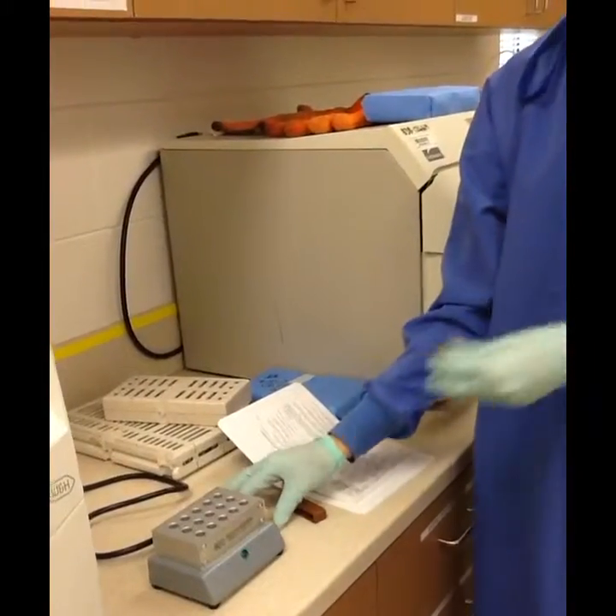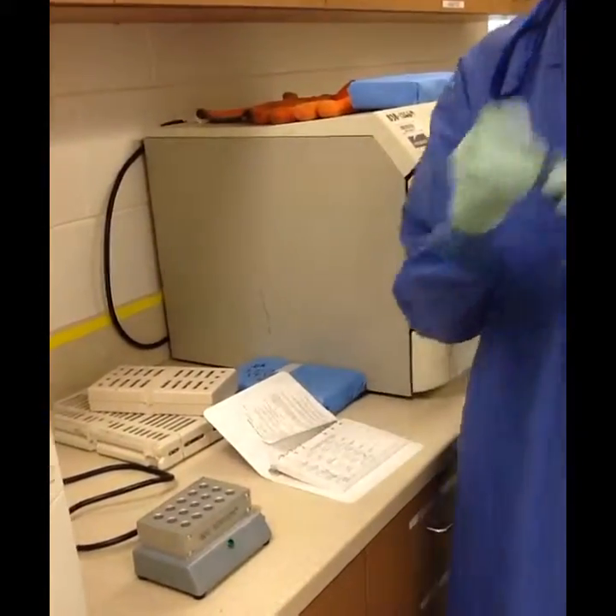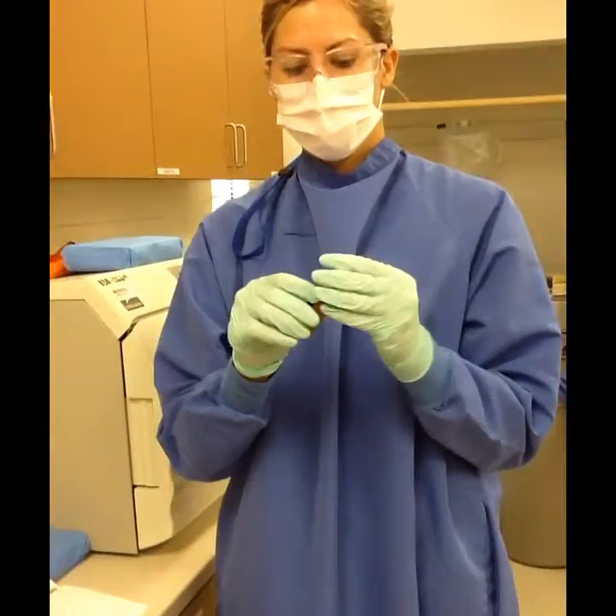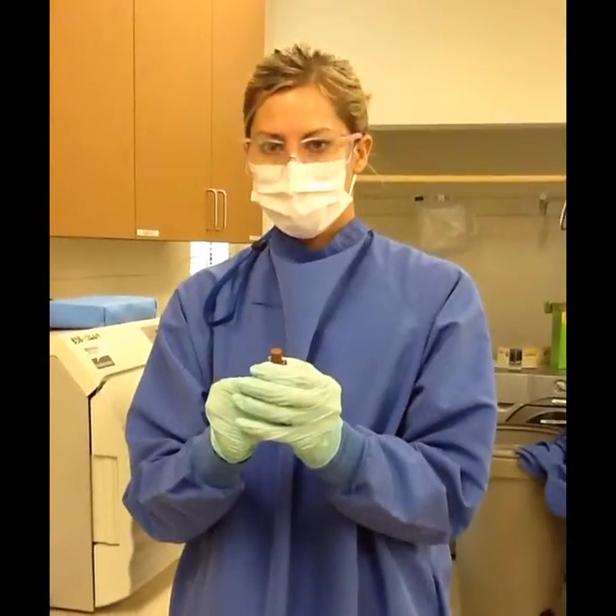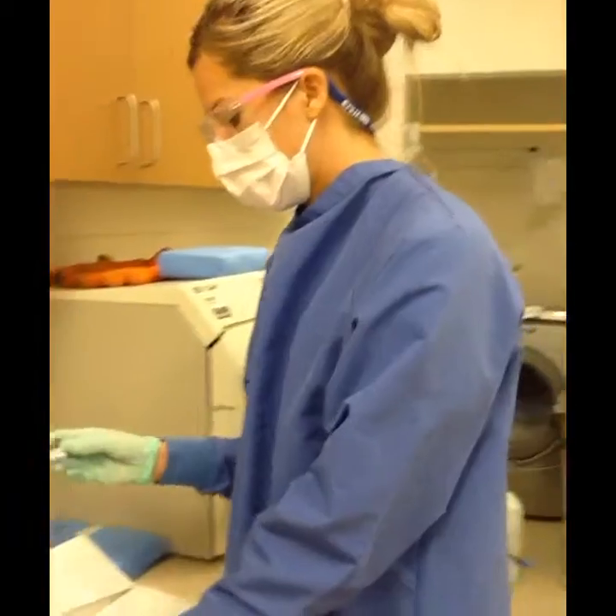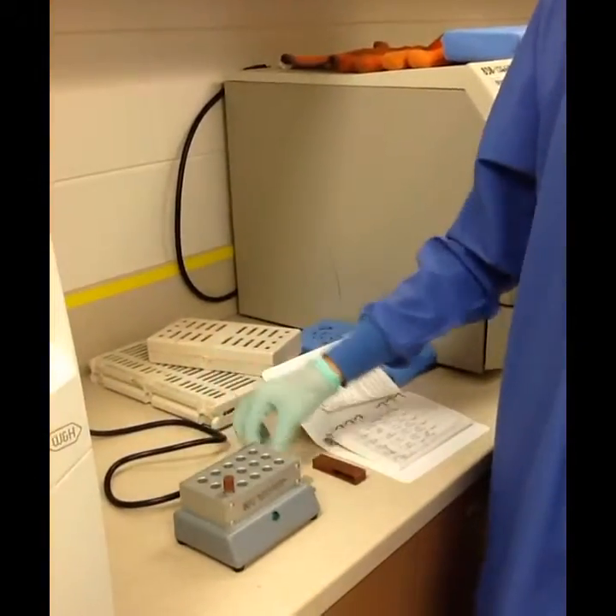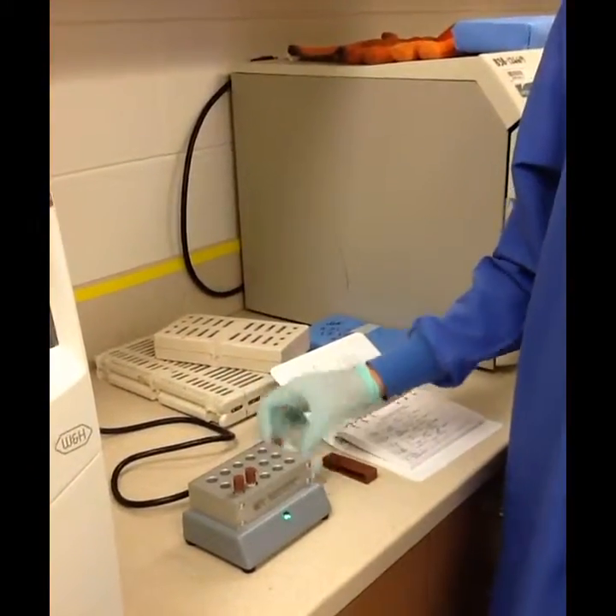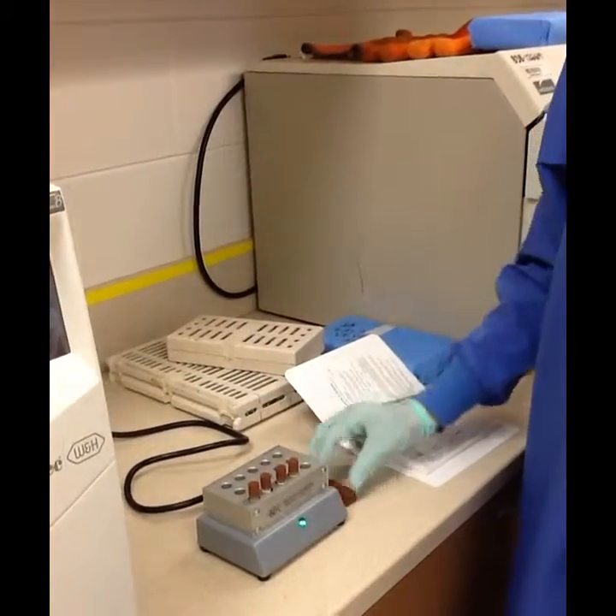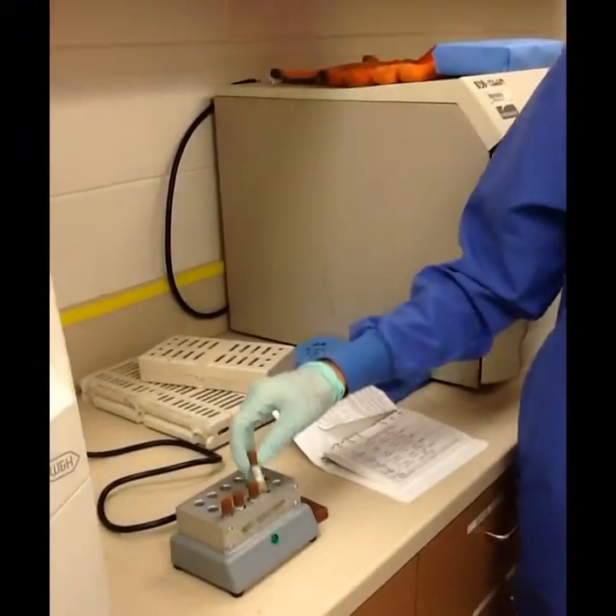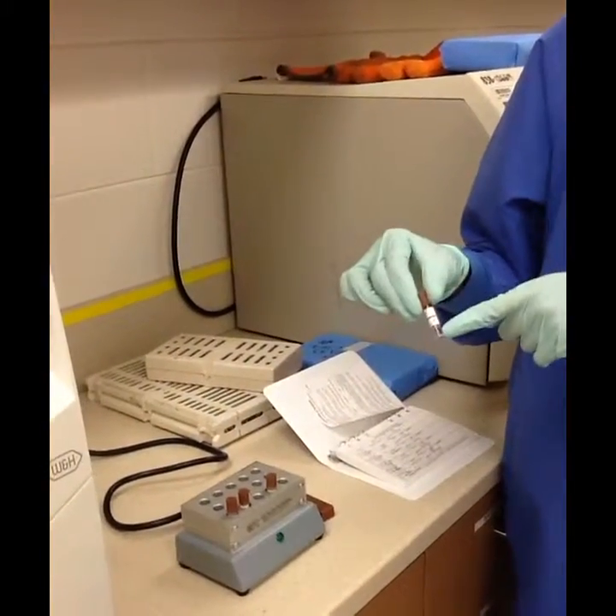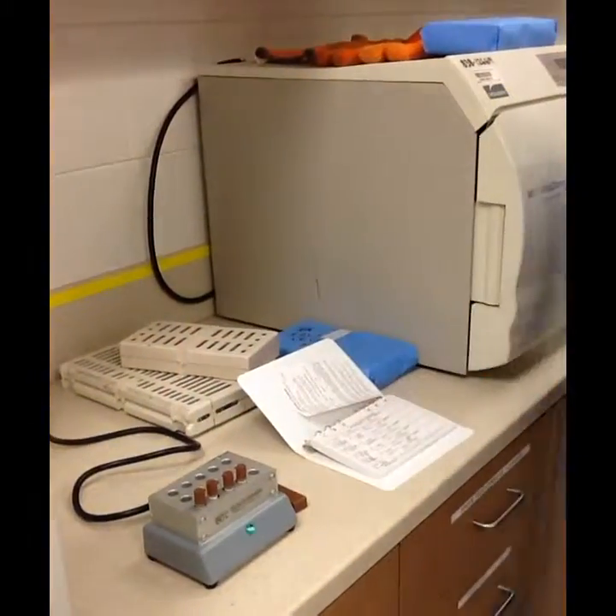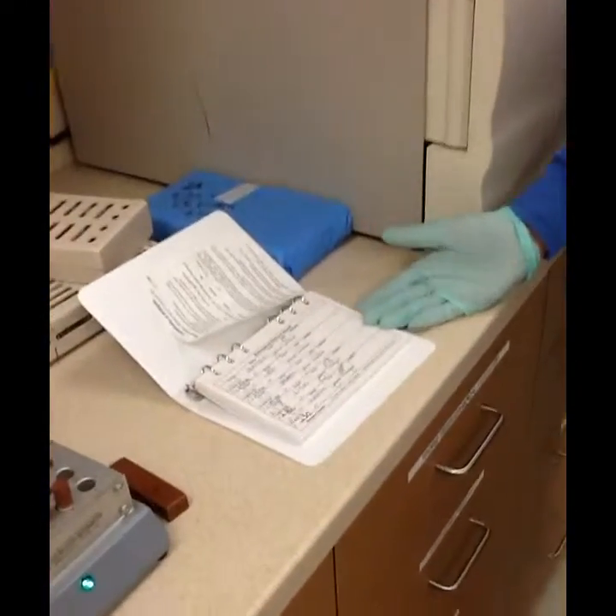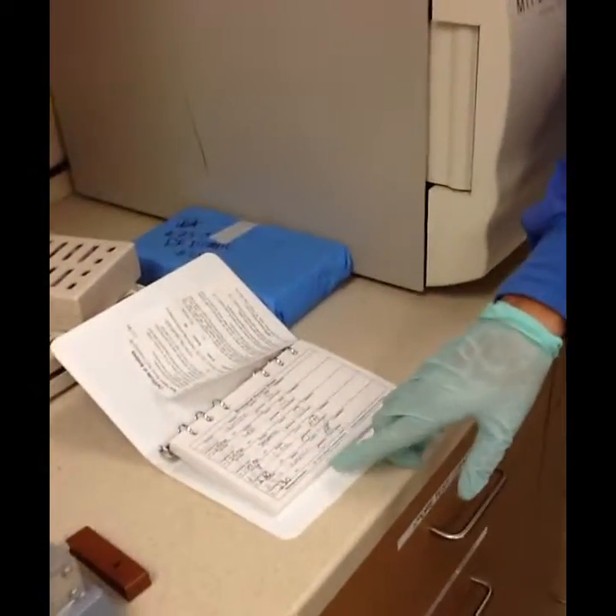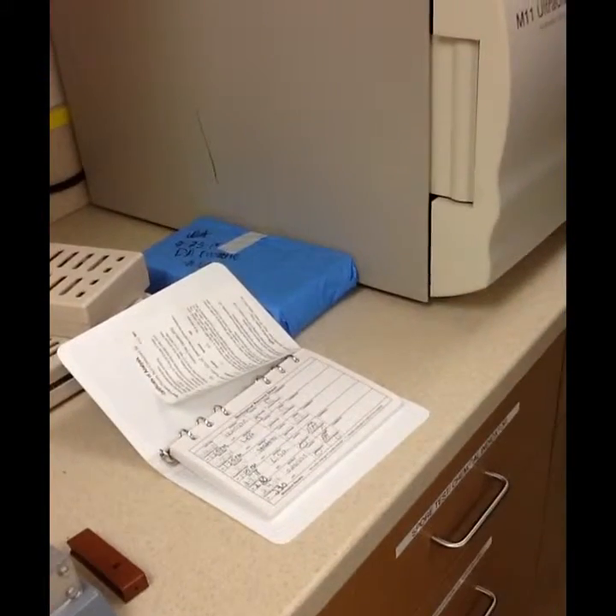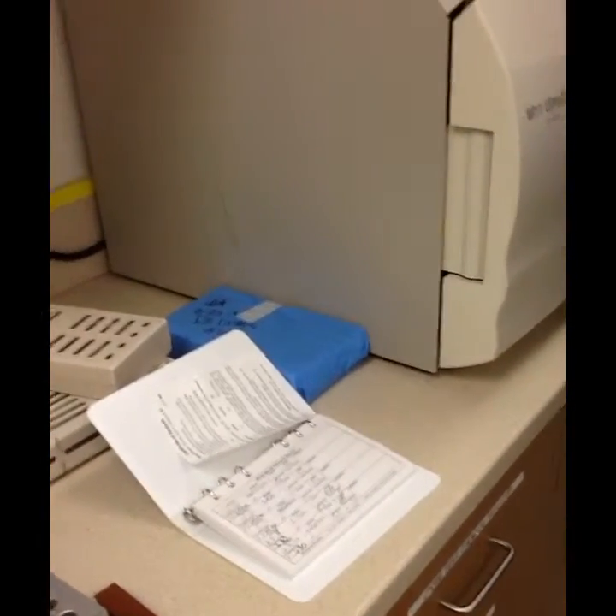After the vials have been through their cycles, crush it by placing the vial in the crusher with the head out. Place the crushed vials and the control vial into the incubator and incubate them for 24 hours. A positive result will be yellow after incubation, and a negative result will be purple after incubation. Be sure to make detailed records in the record-keeping book. This should include the time, date, and final results. After you record your results, you should dispose of the vials in an appropriate sharps container.